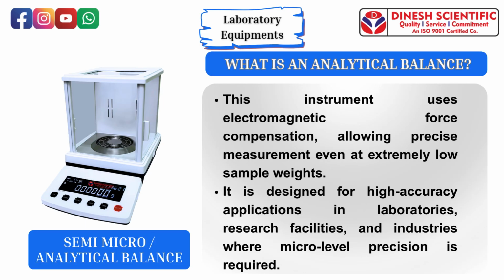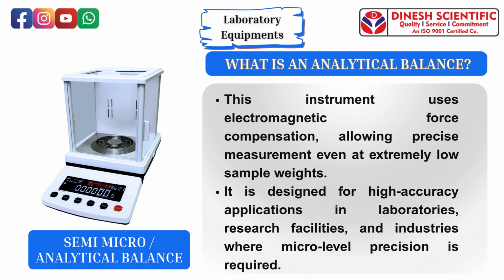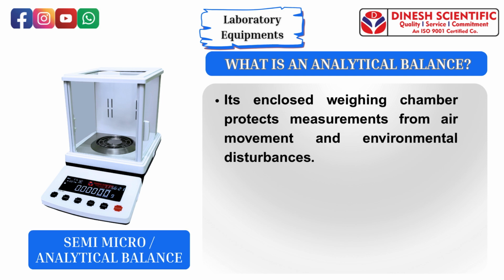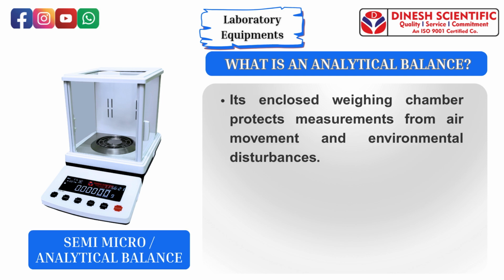What is an analytical balance? This instrument uses electromagnetic force compensation, allowing precise measurement even at extremely low sample weights. It is designed for high-accuracy applications in laboratories, research facilities, and industries where micro-level precision is required. Its enclosed weighing chamber protects measurements from air movement and environmental disturbances.